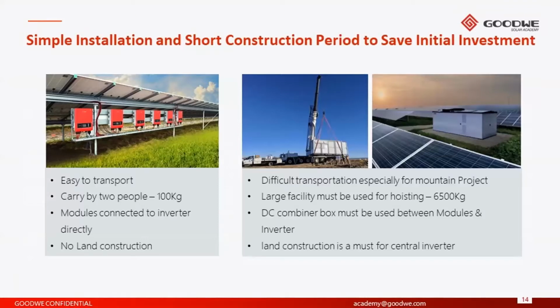So for string inverters, which could be from anywhere from 20 kilograms to 100 kilograms, it doesn't take much heavy machinery to install the inverter. So on the left, as you can see, a number of smaller inverters are installed next to each other on a custom-built rack. There's no need for concrete padding or special mounting for the string inverters. You can simply install them on the back of the PV array.